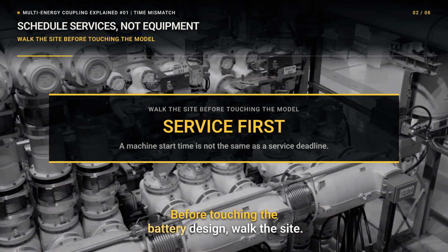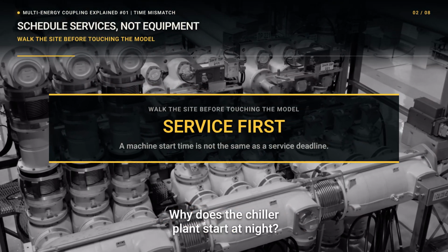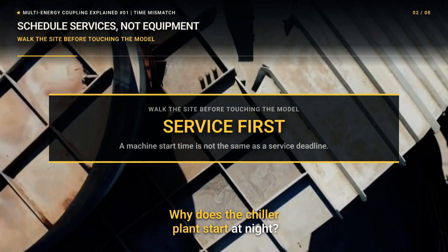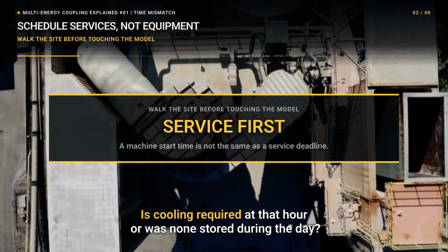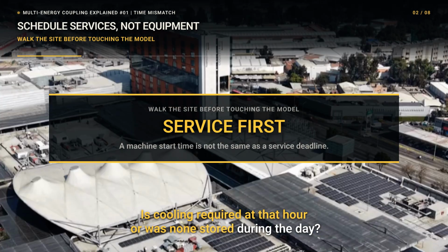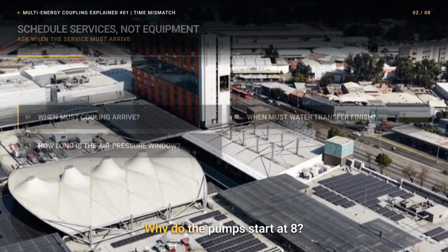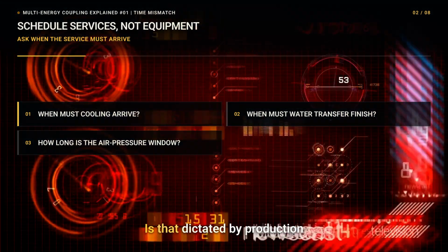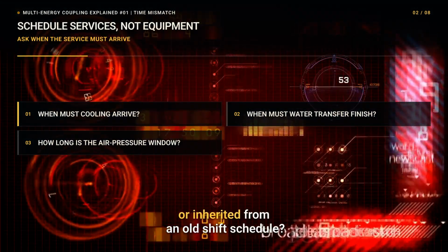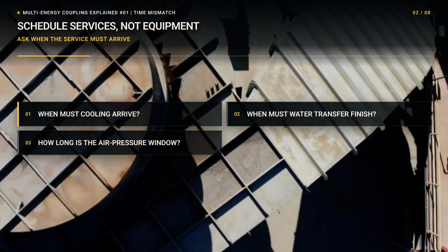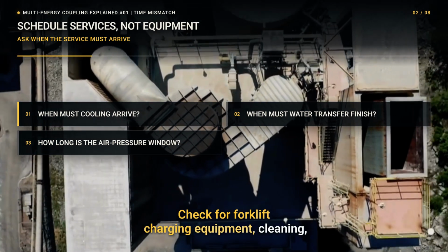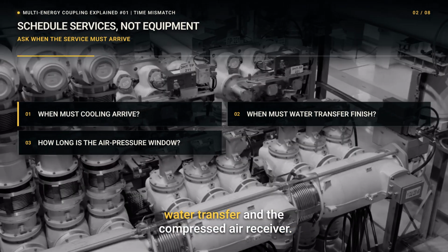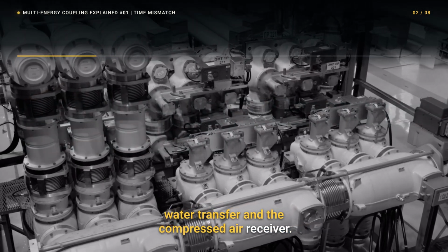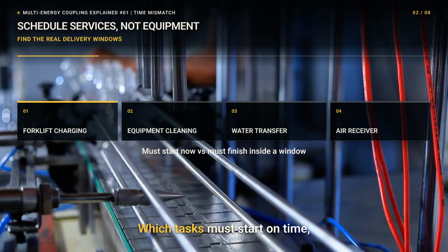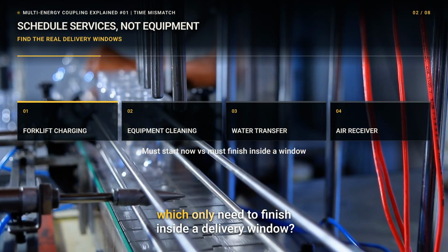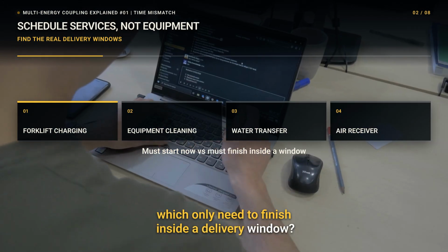Before touching the battery design, walk the site. Why does the chiller plant start at night? Is cooling required at that hour, or was none stored during the day? Why do the pumps start at 8? Is that dictated by production or inherited from an old shift schedule? Check forklift charging, equipment cleaning, water transfer, and the compressed air receiver. Which tasks must start on time? Which only need to finish inside a delivery window?